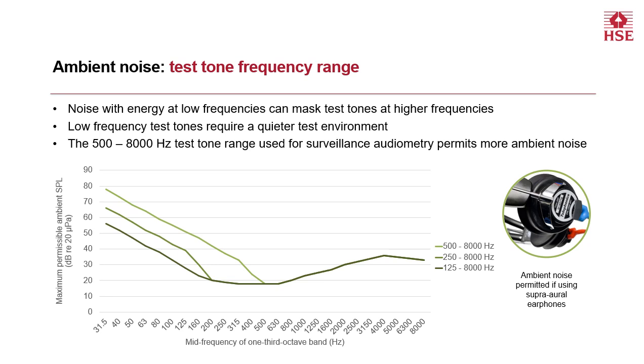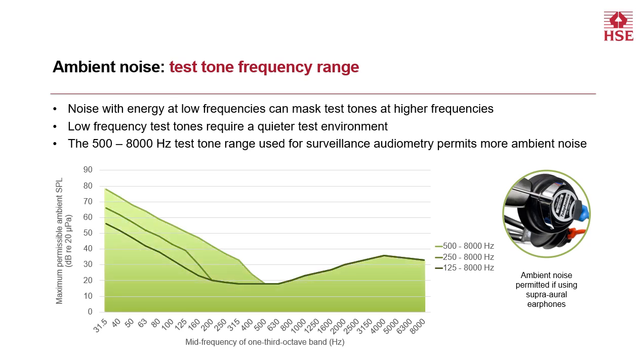Here we have a plot of the maximum permissible ambient sound pressure levels across frequency if we use supra-aural earphones. The lowest line, which is the darkest shade of green, shows the maximum permissible ambient sound pressure levels if we're interested in testing from 125 Hz upwards. The middle line shows the levels if we're interested in testing from 250 Hz upwards, and the lightest green line is for test tones from 500 Hz upwards. Ambient noise levels falling within the green shaded area are permitted for surveillance audiometry. So far so good. We've made it a little easier for ourselves by not testing at 125 Hz or 250 Hz.